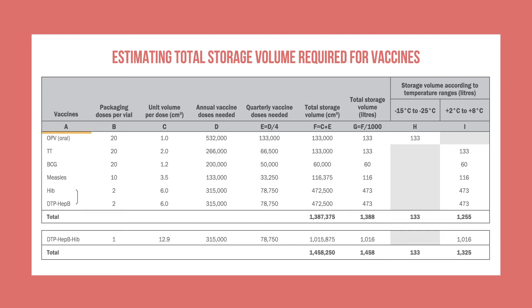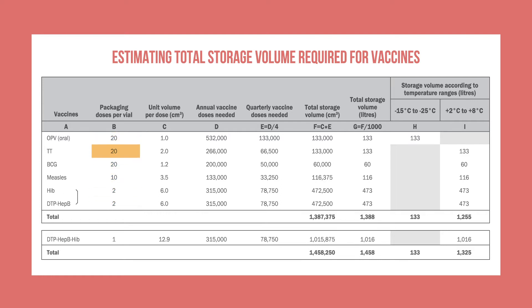First, list every vaccine in the schedule. If diluents need to be refrigerated, they should be included in the list. For each vaccine, list the number of doses per vial according to the presentation being used. Here, the district has ordered tetanus toxoid, or TT, with 20 doses per vial.